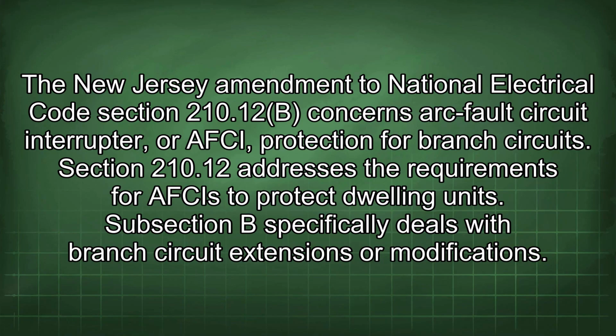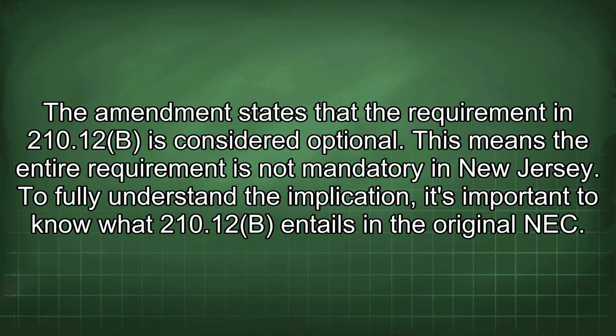The New Jersey Amendment to National Electrical Code Section 210.12(B) concerns arc fault circuit interrupter, or AFCI, protection for branch circuits. Section 210.12 addresses the requirements for AFCIs to protect dwelling units. Subsection B specifically deals with branch circuit extensions or modifications. The amendment states that the requirement in 210.12(B) is considered optional. This means the entire requirement is not mandatory in New Jersey.